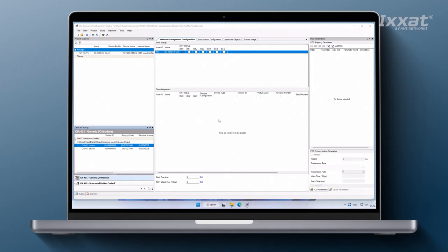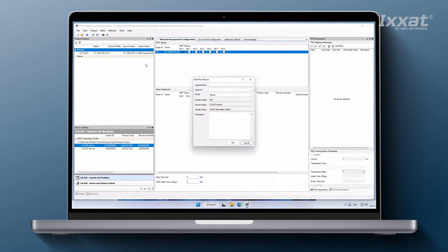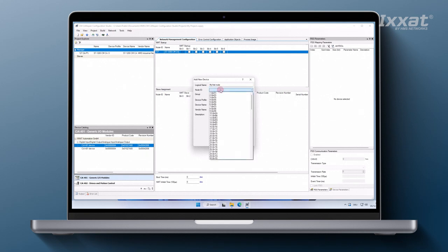To add a device to the CanOpen network, open the corresponding navigation field in the device catalog, select the device to be added to the network description and drag it into the project explorer window. For each device a logical name has to be assigned and we have to define the CanOpen node ID and the group to which the device will be added to.